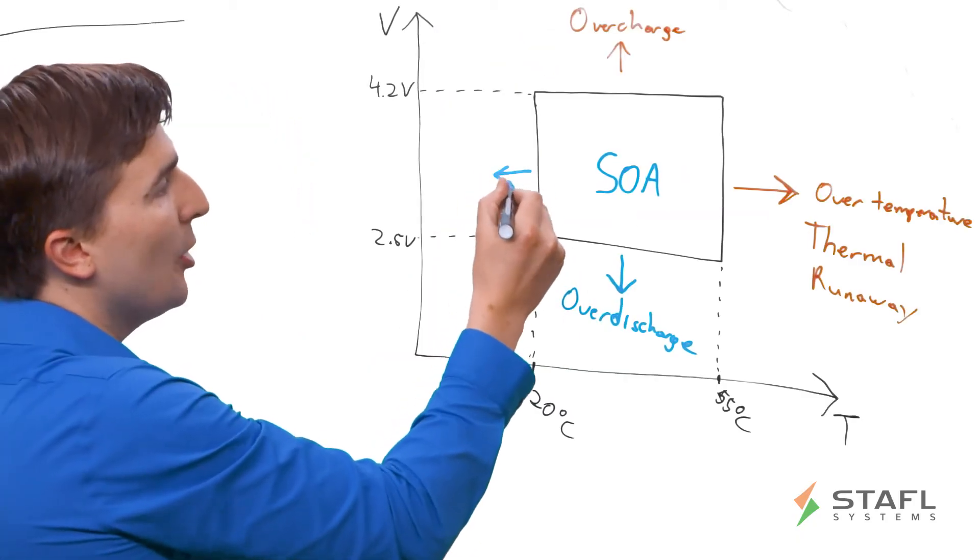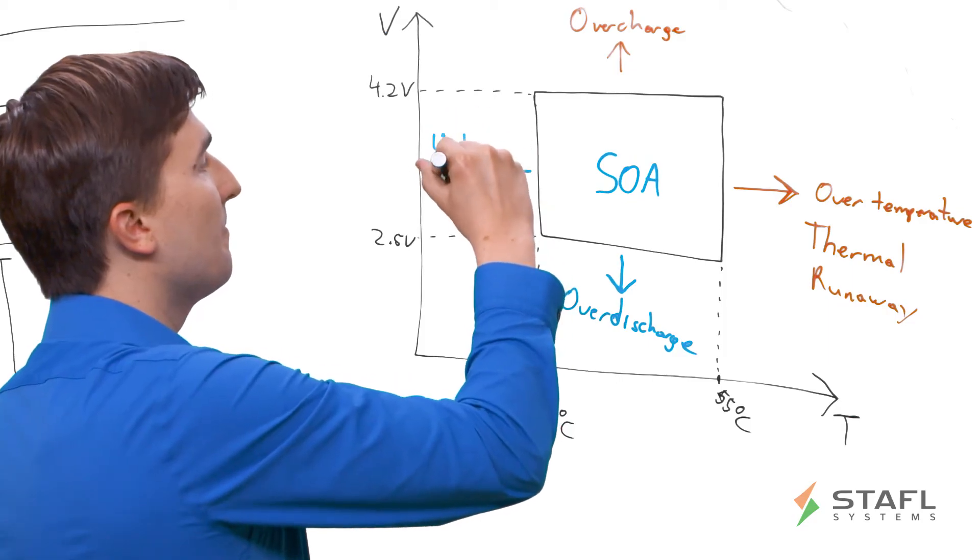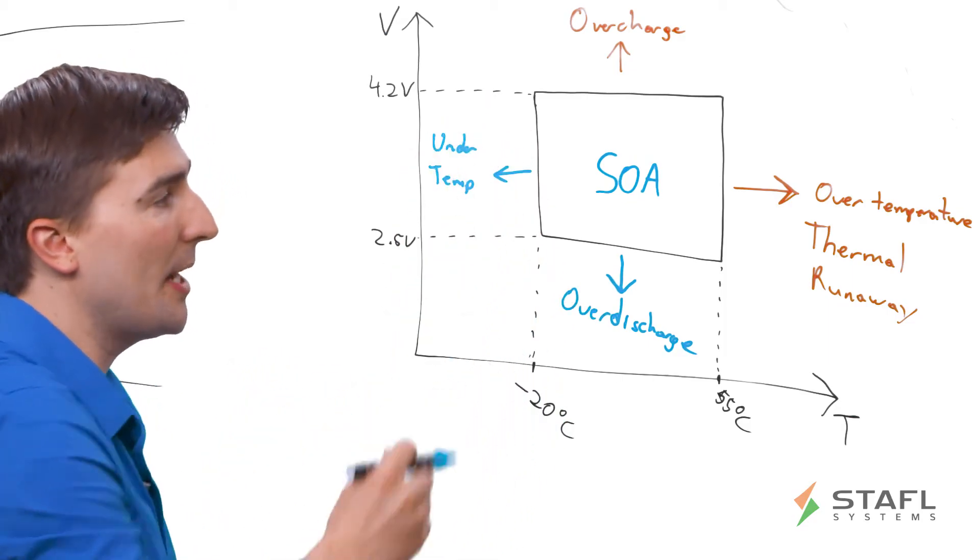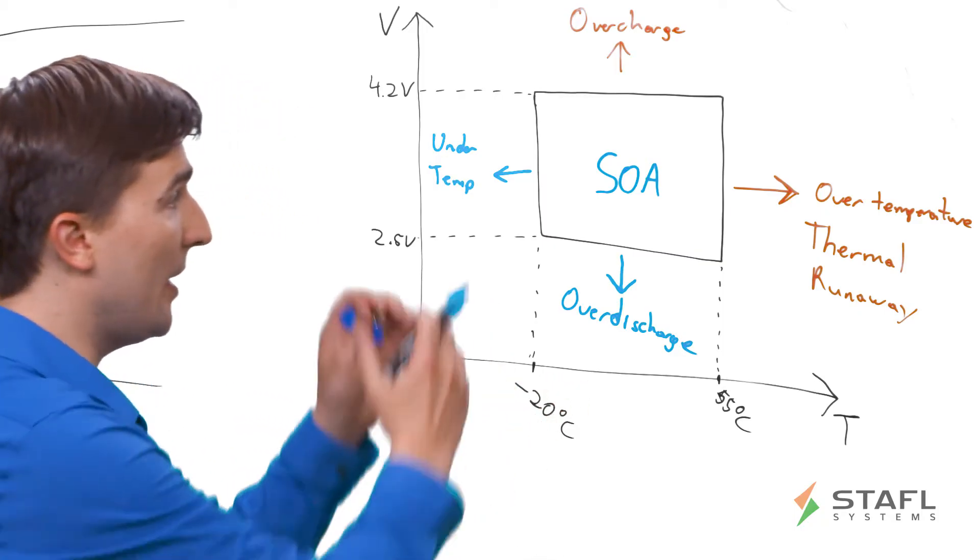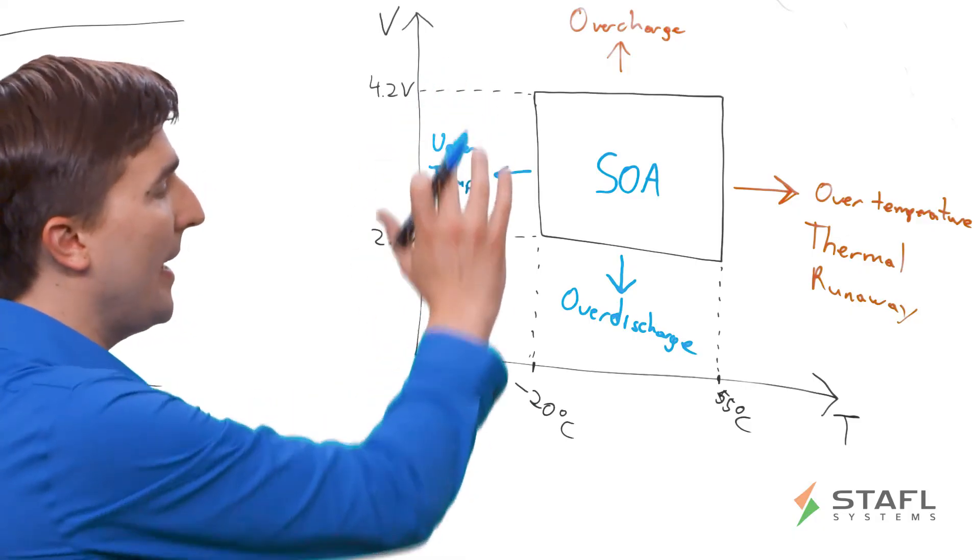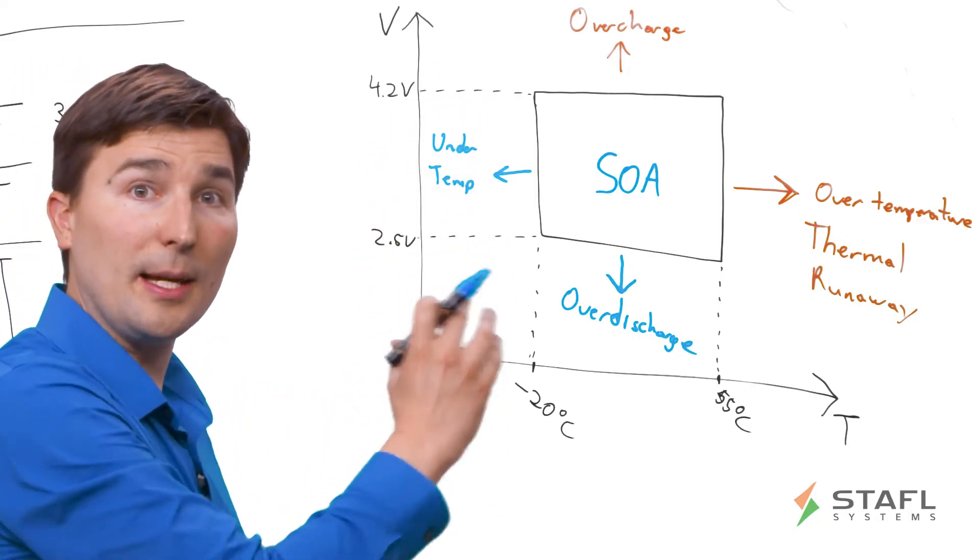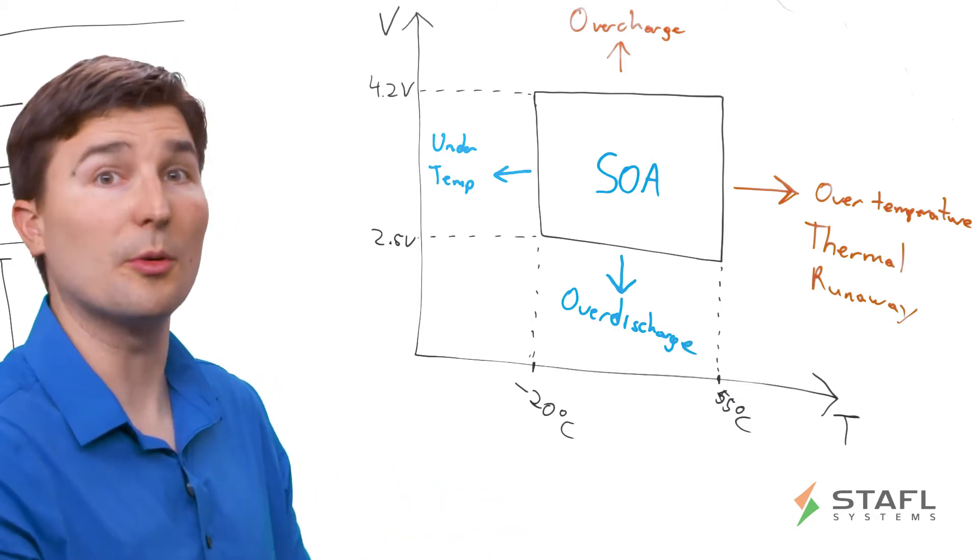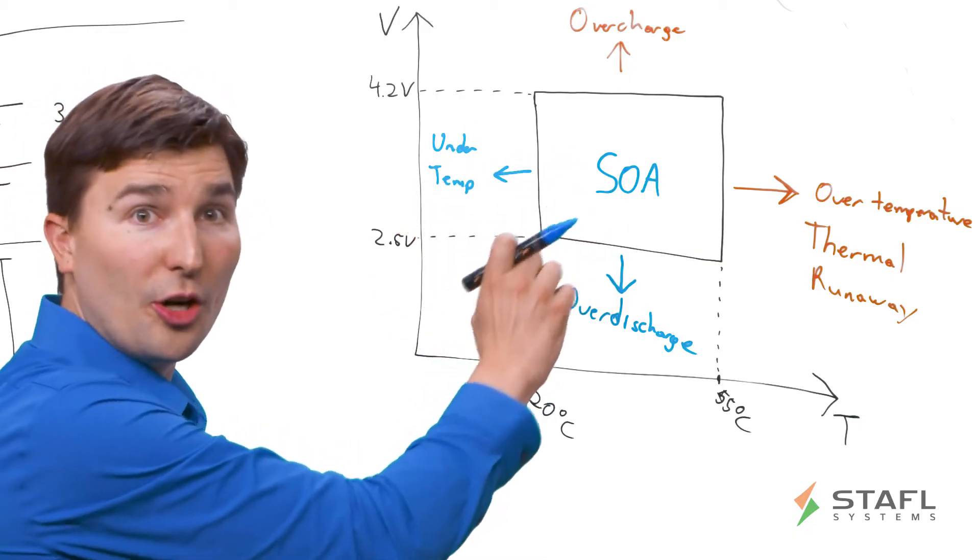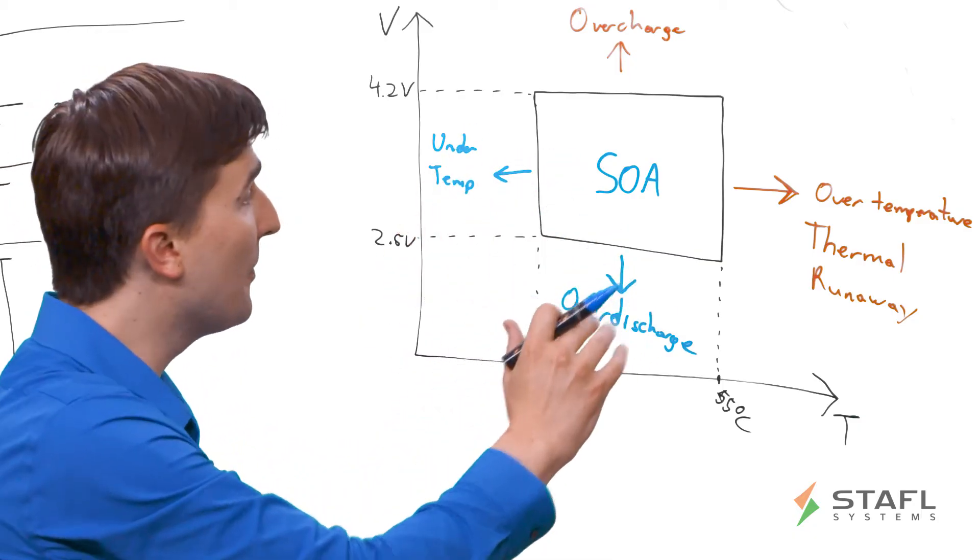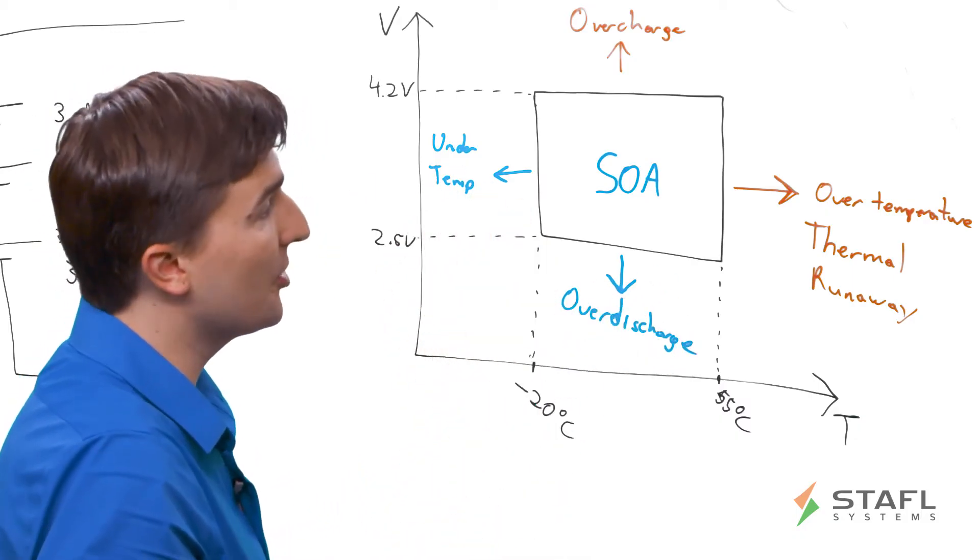Likewise, if you go to what's called the under-temperature case, this is where you have a cell that's less than, say, negative 20 degrees C, and you're still trying to charge or discharge. And at these cold temperatures, the electrochemistry within the cell is no longer able to actually move the ions from the anode to the cathode or vice versa. So you're actually not able to efficiently get charge into or out of the cell. And this can also lead to lithium plating and the issues that we just discussed with the over-discharge scenario.